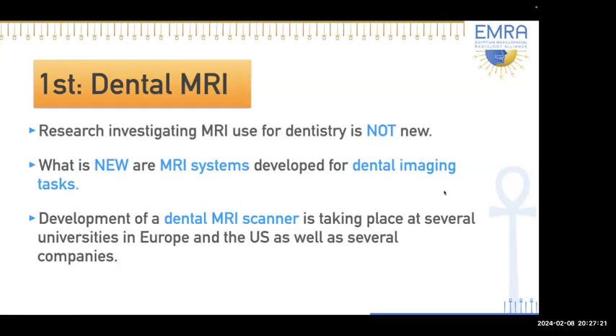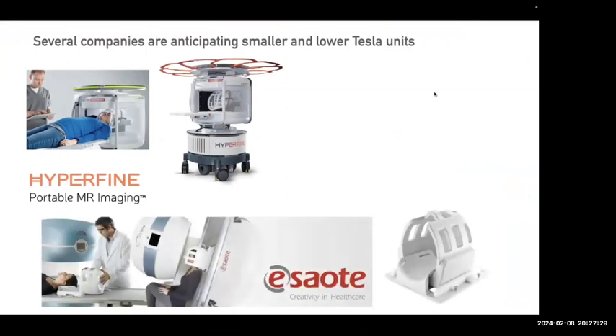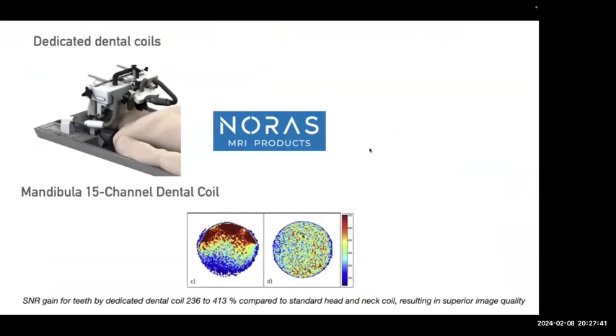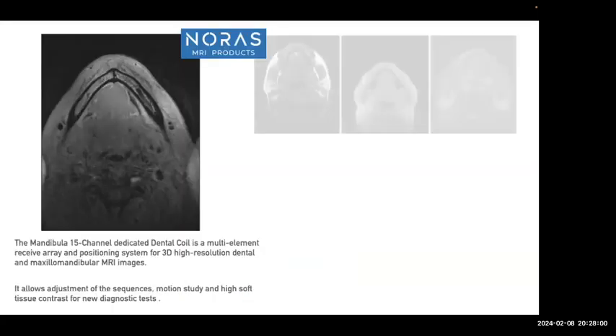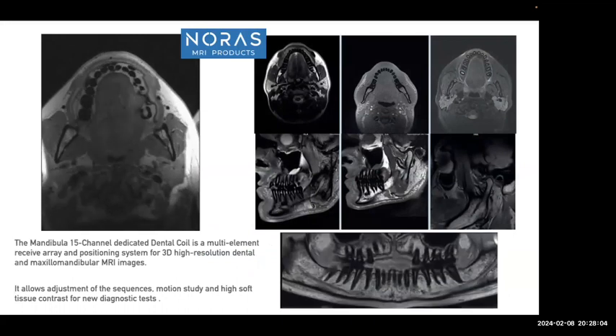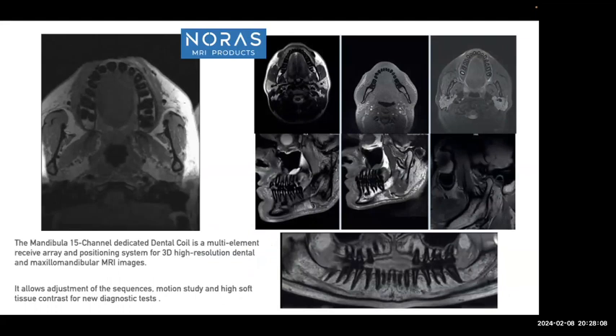To summarize, research investigating MRI use in dentistry is not new, but what is new is MRI systems developed specifically for dental imaging tasks. Several companies are anticipating smaller, lower-tesla units for dental purposes, along with dedicated dental coils such as the NORAS Mandibula 15-channel dental coil, which shows a signal-to-noise ratio gain of 236 to 413 percent compared to a standard head and neck coil — resulting in superior image quality and enabling 3D high-resolution dental and maxillomandibular MRI images.